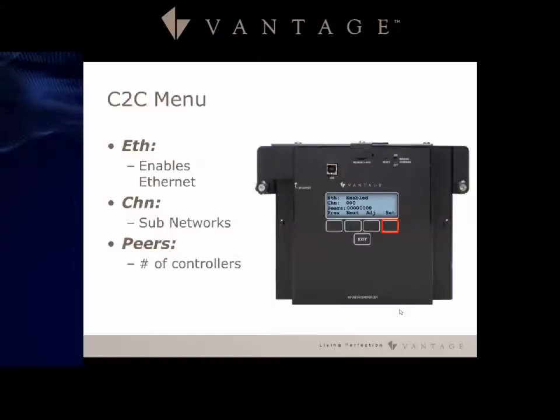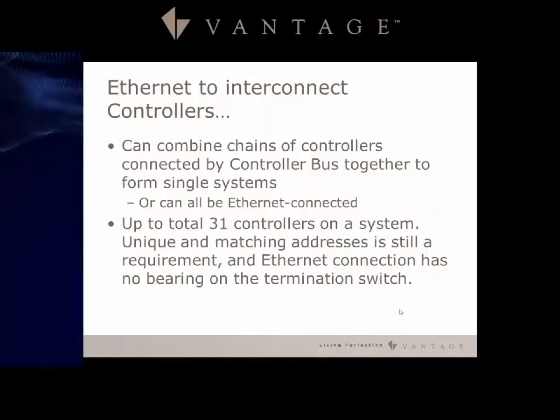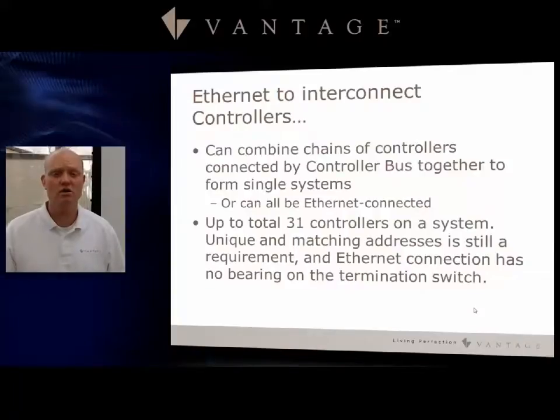Peers gives you the ability to look at the hex code and verify that the number of controllers is correct, if you know how to work through the hex code algorithm. You can mix master bus and ethernet bus systems — combining chains of controllers connected by the controller bus with ethernet-connected controllers to form a single system. You can have a total of 31 controllers on an ethernet-based system: up to 15 on the master bus, and the remaining 16 via the ethernet bus.